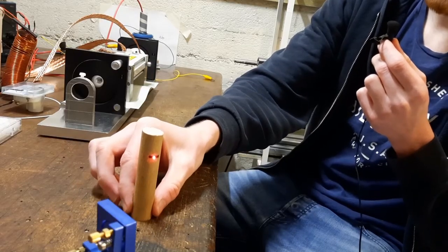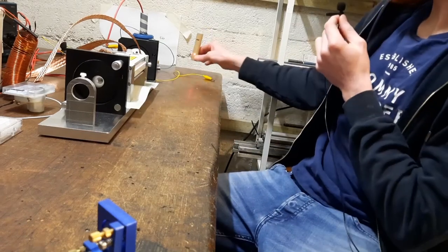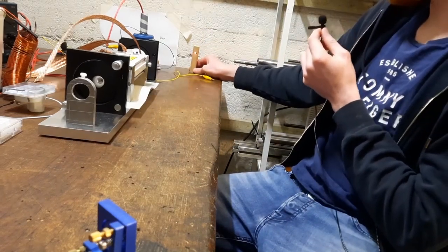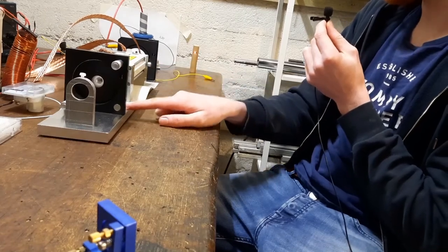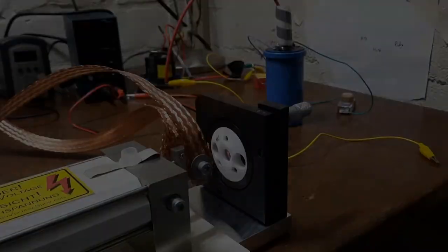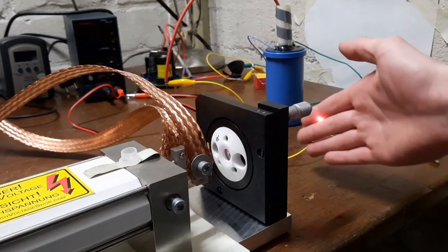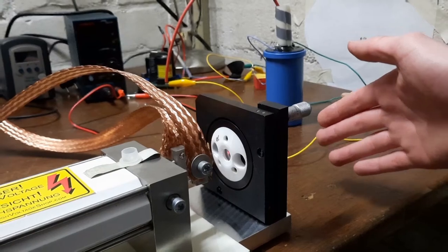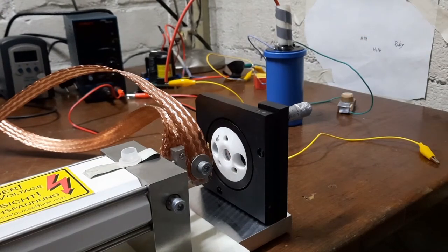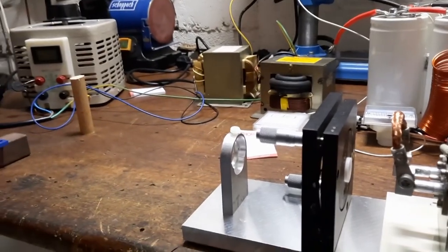Okay, so as you can see this is now aligned quite well. This is now parallel to the table. Now we can start sliding this laser module into this beam. Okay, as soon as we're confident that the laser beam makes it right through all the components. We can actually turn our attention to the outcouple side of the laser.